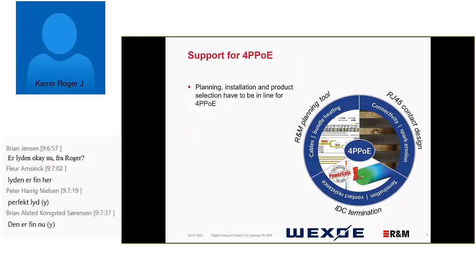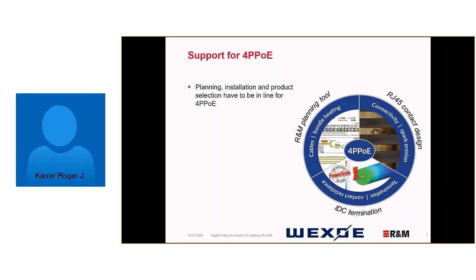Support for four-pair Power over Ethernet is built on three pillars, as shown in this wheel. The first and most important is the contact design and connectivity — specifically spark erosion that can appear when unplugging under load. The second pillar is IDC termination and power safety. The third pillar is planning, which has been the most neglected in the past but is now critical: bundle size and link length both matter for powering remote devices.